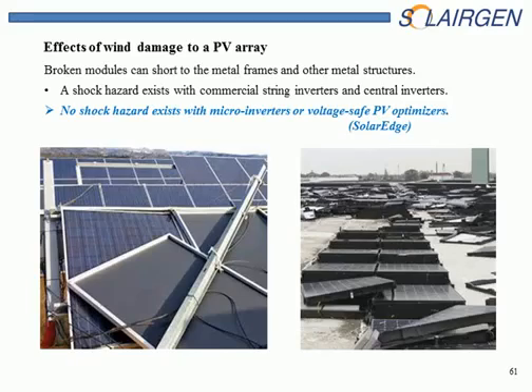So take caution. Wear insulated gloves, insulated boots, everything, and you probably can operate around this without too much of a hazard. Shutting down the whole PV system won't make any difference. If it's a string inverter system, there's high voltage everywhere.